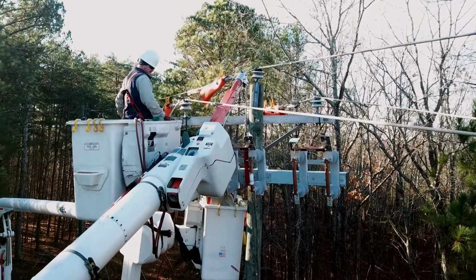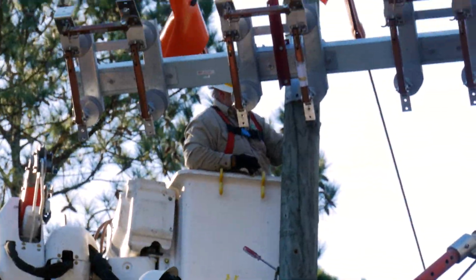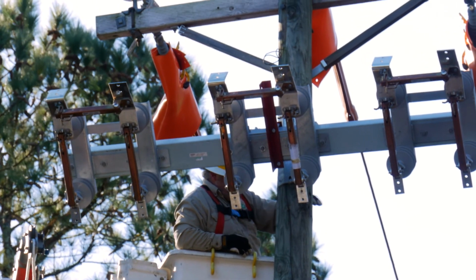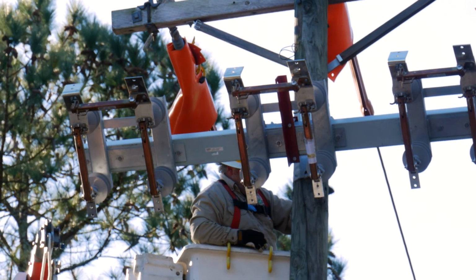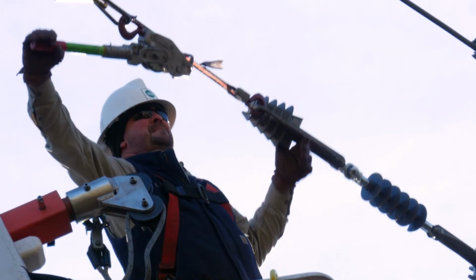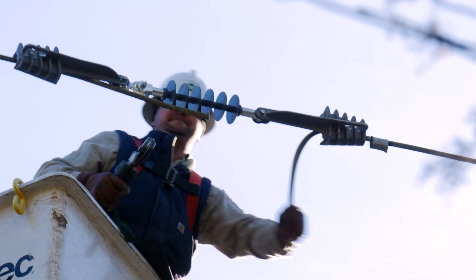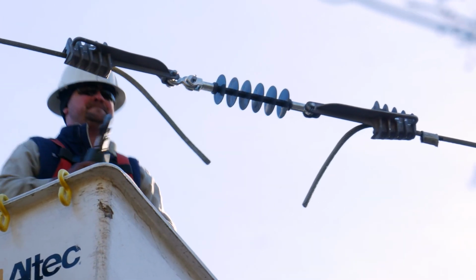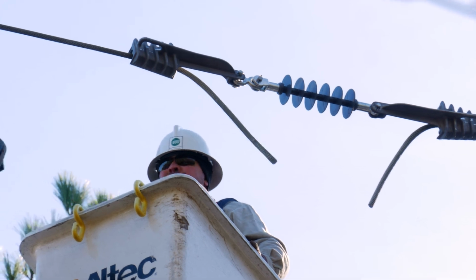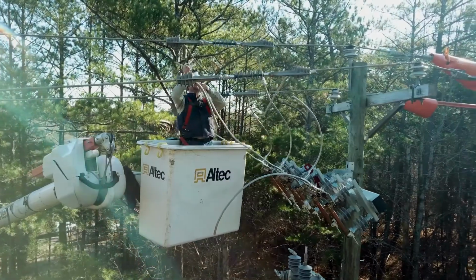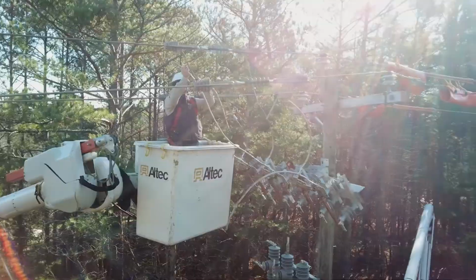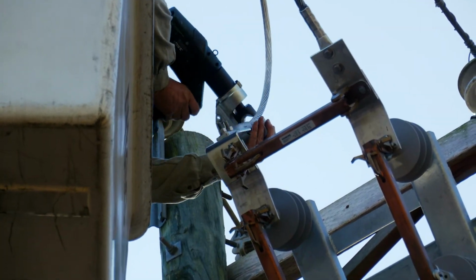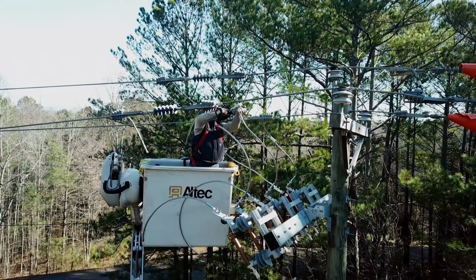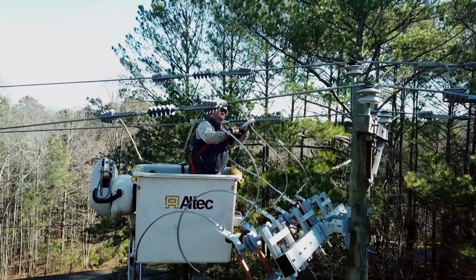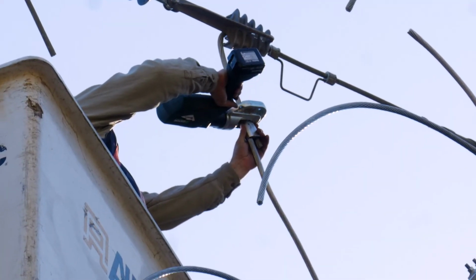In this scenario, the utility utilizes 3 bypass disconnect switches pre-mounted on a crossarm to expedite installation. Once the bypass disconnect switches are installed, the utility must then prepare to run jumpers from the main line down to them. This utility utilized dead-end bells to cut the line and then proceeded to prepare the jumpers from the dead-end bells down. If the line construction already has double dead ends, then the line jumpers should be removed and jumpers made up from each side of the pole down to the bypass disconnect switches.